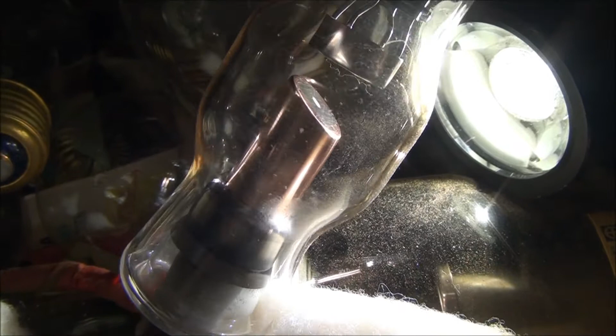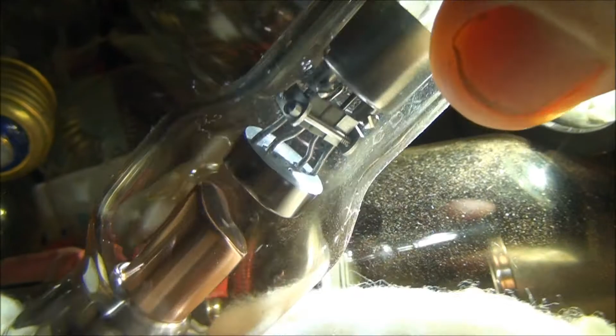You can see that one. It's got a tungsten insert buried in the copper anode. The copper helps conduct the heat out of an anode during operation, so the tube doesn't overheat. And of course they're immersed in special high voltage oil for electrical insulation and heat properties. That's that one. Put it in there.